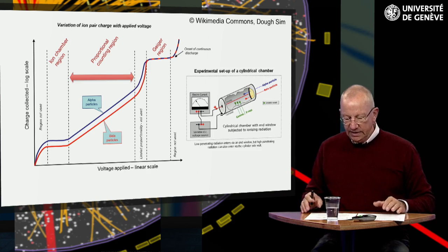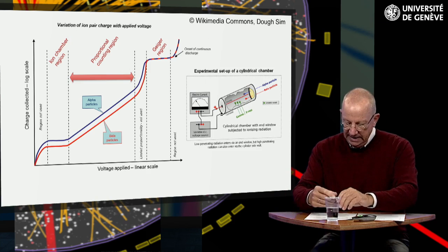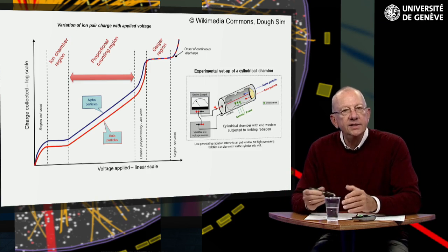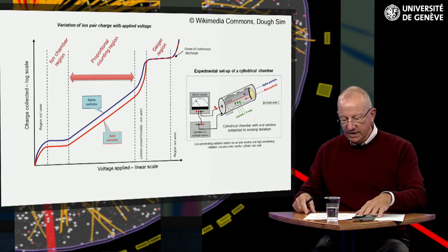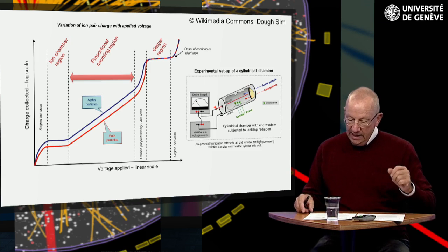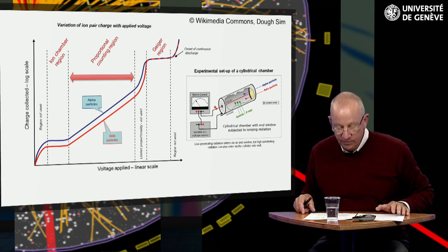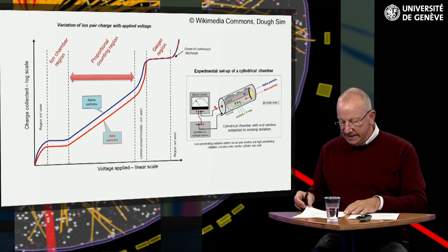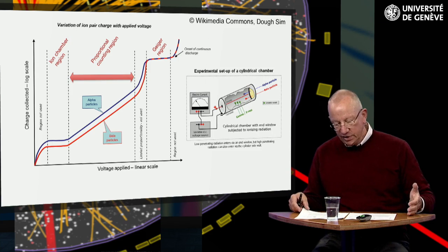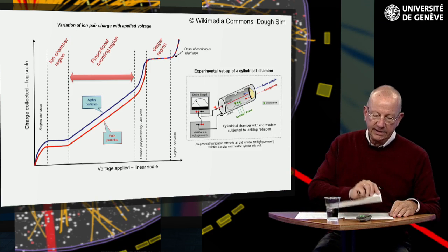The advantage of using this region is that there is no need to have very low noise electronics, since there is internal amplification in the detector itself. The disadvantage is that the energy resolution is worse because of fluctuations in the amplification process. These fluctuations are mainly due to instabilities in external parameters like the high voltage, the temperature, the pressure, etc.